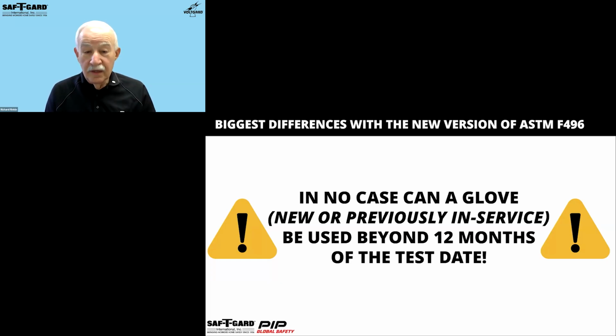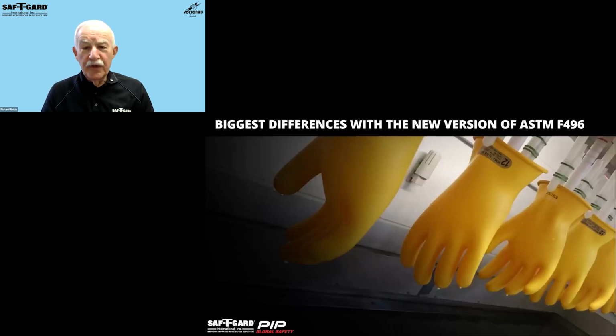So again, to make it clear, rubber insulating gloves, whether new or previously issued for service, need to be electrically tested 6 months from the issue date or 12 months from the last test date, whichever comes first. Periodic retesting of rubber insulating gloves should be performed at the proof test voltage that was indicated on that label and on the chart that we showed earlier. This ensures that they're still safe, using specialized equipment designed to gradually increase the voltage to that desired test level.